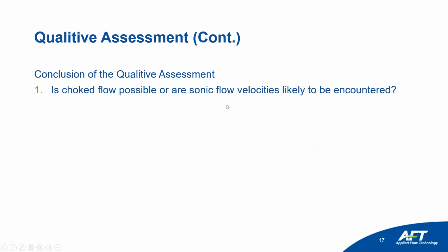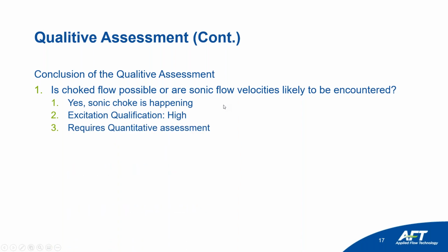So answering the questions, the conclusion of the qualitative assessment is: is choked flow possible, or are sonic flow velocities likely to be encountered? The answer is yes, sonic choke is happening. Excitation qualification is high, which means it requires a quantitative assessment to make sure it's not a failure, or to make the corrections needed to lower the risk.